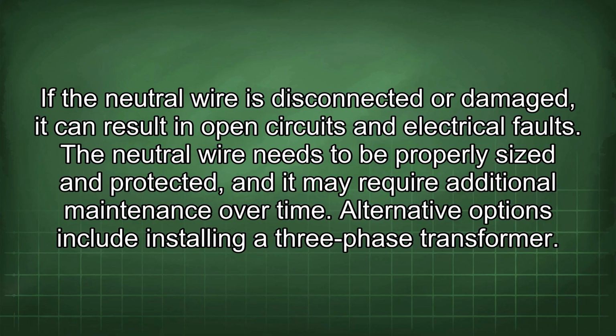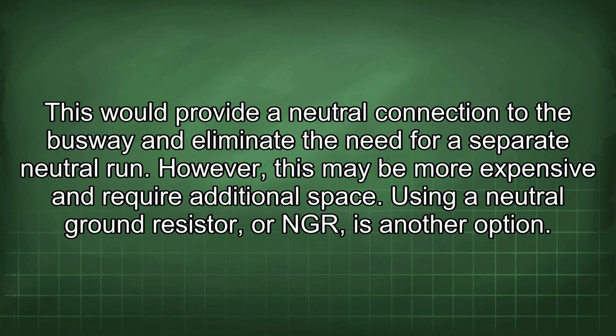Alternative options include installing a 3-phase transformer. This would provide a neutral connection to the busway and eliminate the need for a separate neutral run. However, this may be more expensive and require additional space.